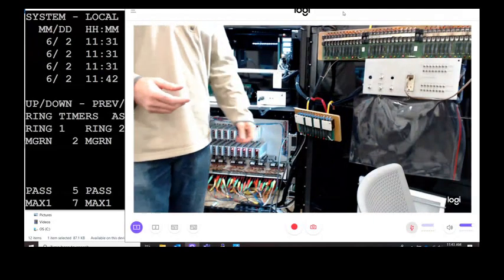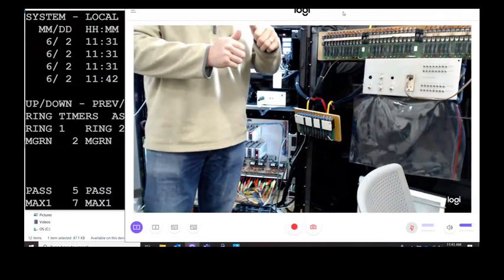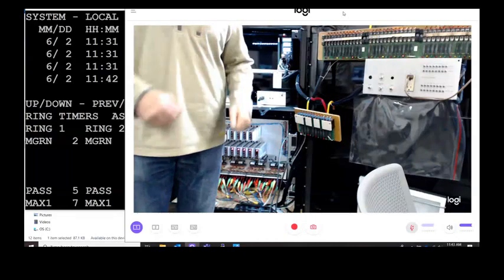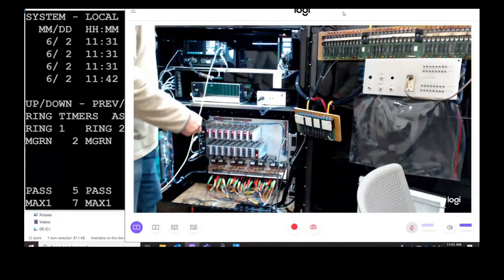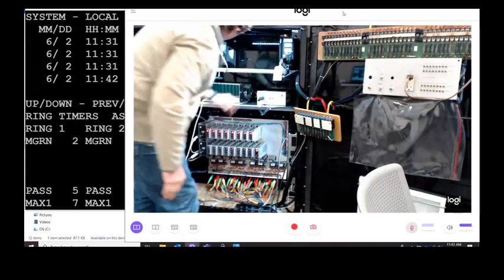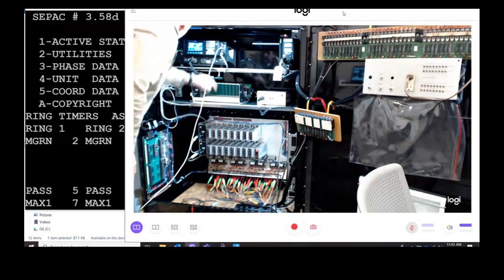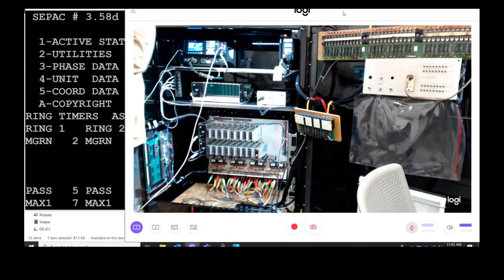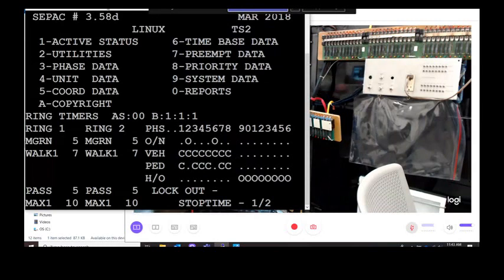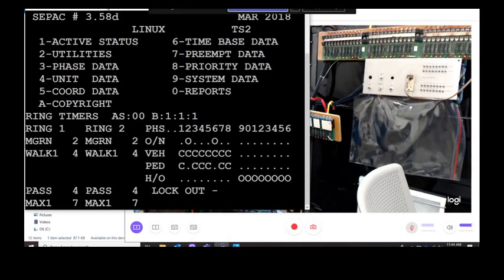In the old NTS1, you had that other little smaller card that used to be able to pop in and out. It wouldn't give you that failure, but basically you could kind of tell when that thing wasn't in. So we'll put this back in. Feel it pop. Counting down my flash time. So we count down, we're still on the stop time. I hit the reset, and we're gonna pop and come back on. So, like I said, that's kind of an easier one. Again, it just means that the card's not in all the way.